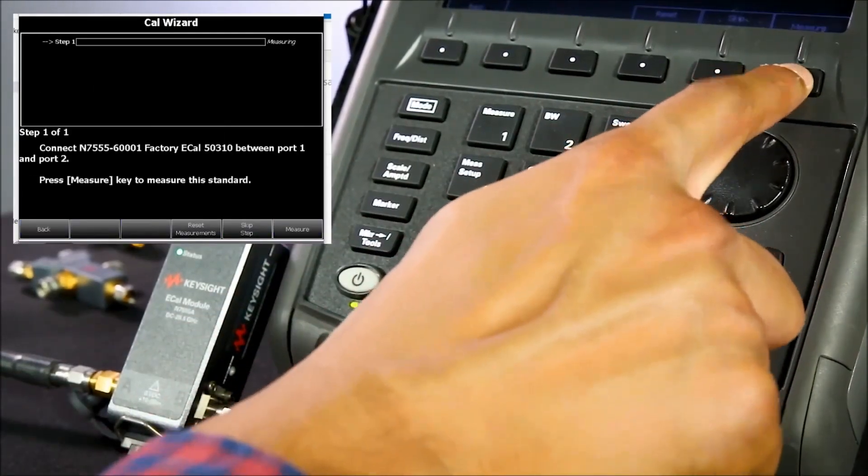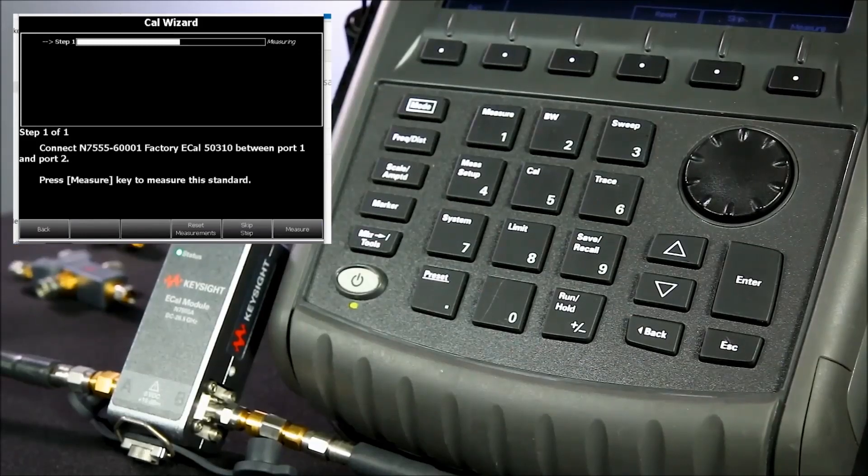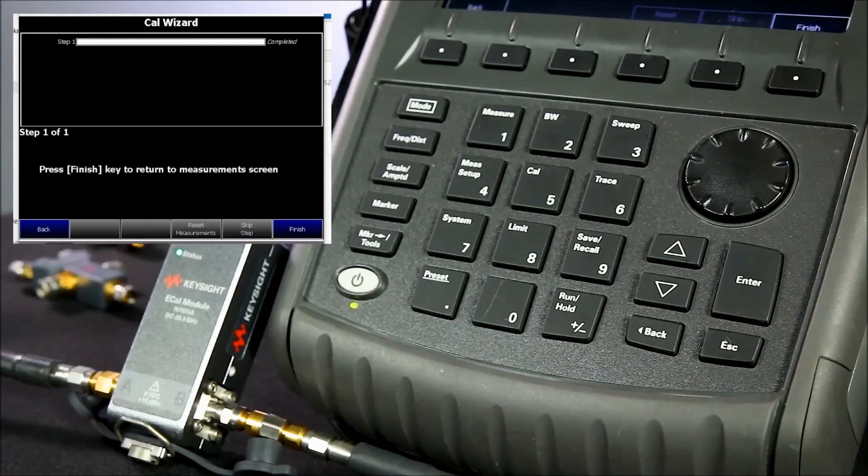and the instrument is running through all of the seven calibration steps automatically without requiring any more connecting or disconnecting. Wow, it's that fast? And we're done!